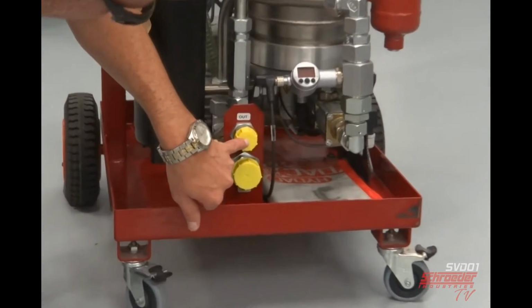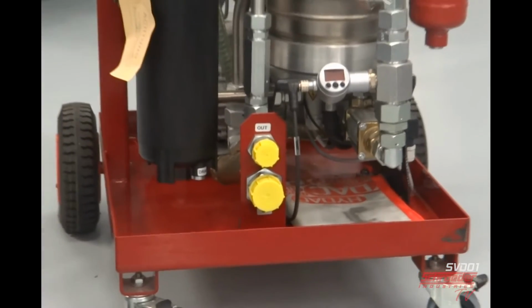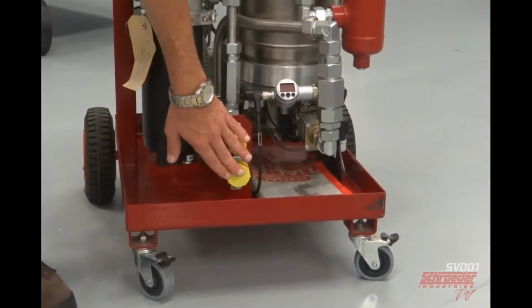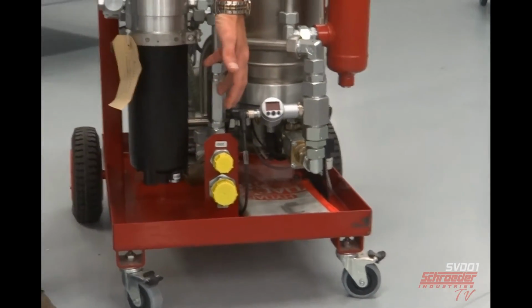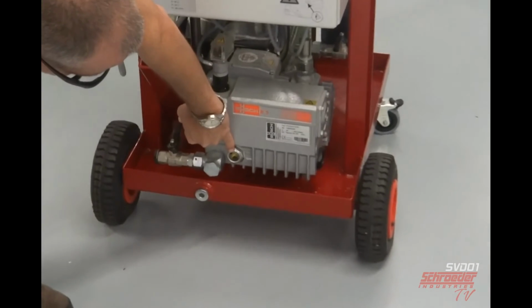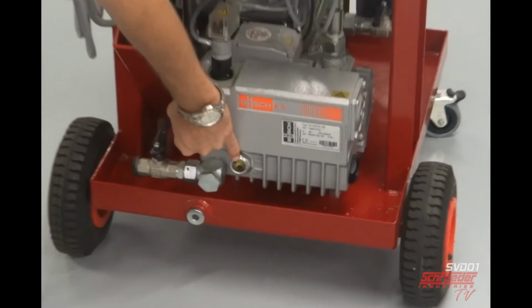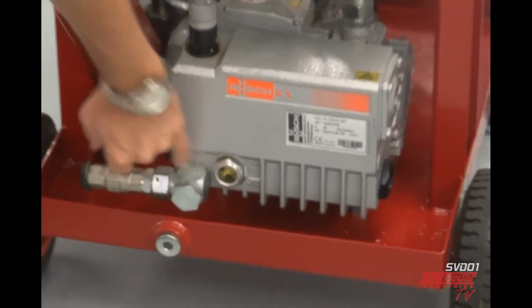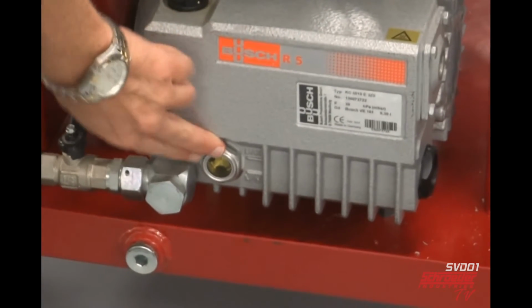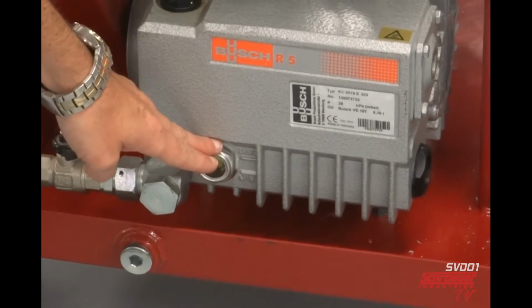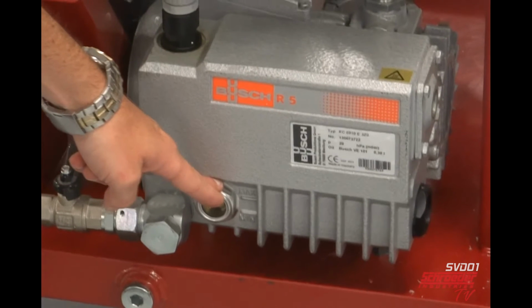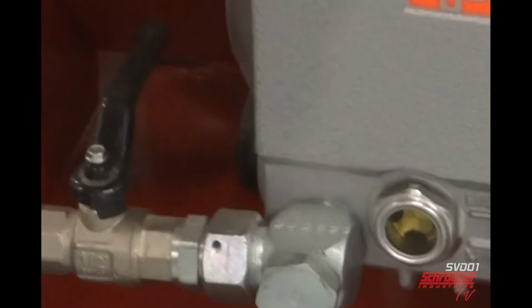Before you start the system, you want to ensure your hydraulic system connections are tight. Make sure they are tight to prevent any leakage that may occur from a loose connection. Make sure, after every 8 hours of operation, you check the oil level of the vacuum pump before you start up the SVD. There's an indicated minimum and maximum line, so it should always be full. There's also a gauge to show when you need to change the actual filter element located on the side of the vacuum pump as well.